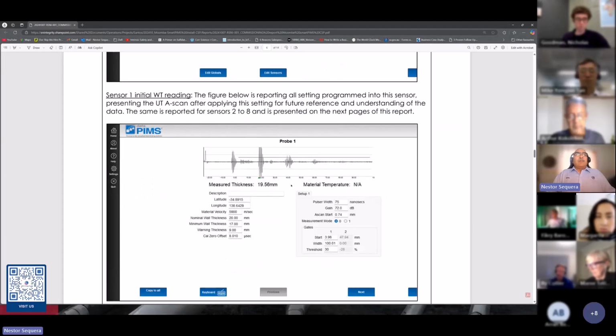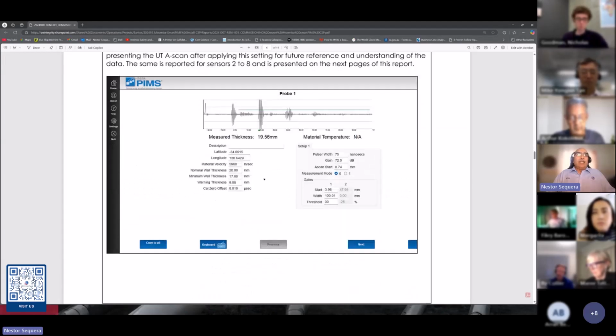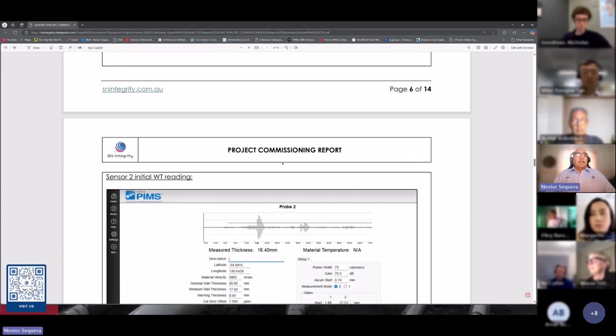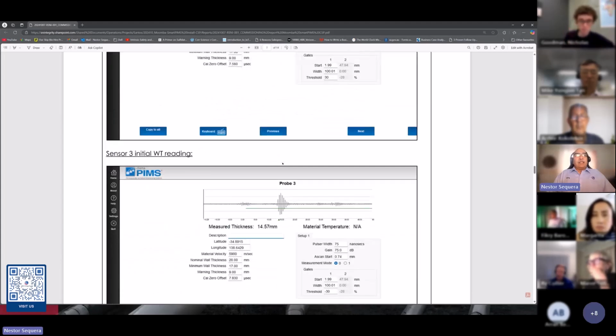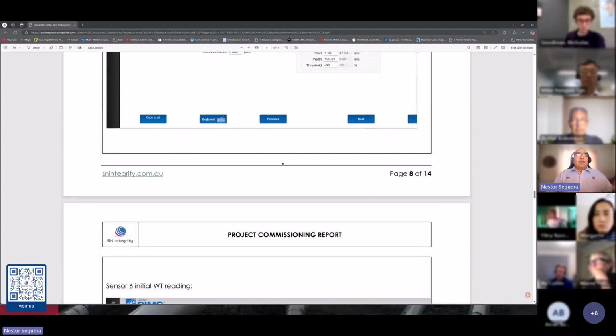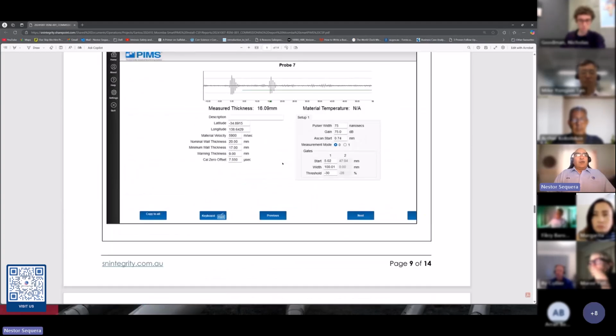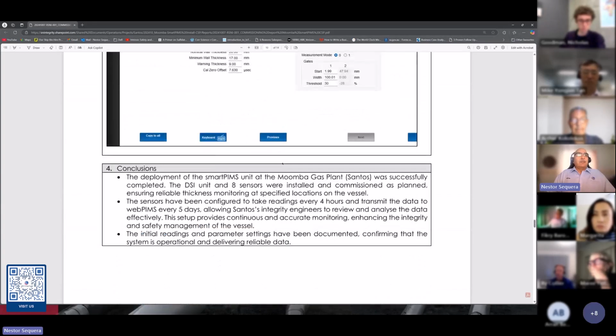As I mentioned, each probe is independent, so we go into each probe and calibrate it, including the A-scan signal. We set the gain of the signal, we set the start and the end of the gate, and all of that is linked to the results. In here, we show the nominal wall thickness, the minimum wall thickness that we mentioned, and the warning thickness that each unit is calibrated on. That is done for the 8 probes that we're setting in this particular application. And all of that, as I said, gets documented and issued to the customer as a final commissioning report.